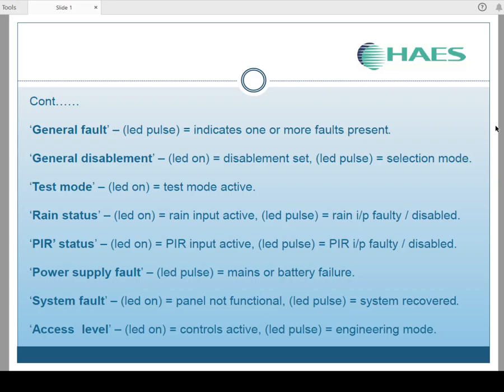Test mode, similarly, if the LED is on, it means you're in the test mode or test mode is active. If the rain status LED comes on, it means the rain input is active. If it starts to pulse, it means the rain input is faulty or disabled. Similarly with the PIR status, if the LED is on, it means the PIR is active. If the PIR LED pulses, it means the PIR input is faulty or disabled.